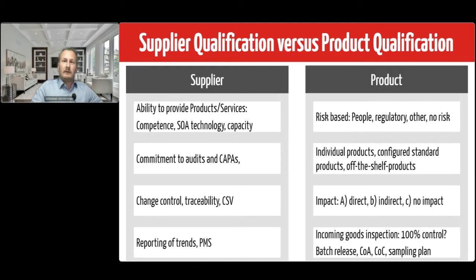And on the product side, they need to have a risk-based approach and estimate what the risk for people is, what the regulatory risks are, other or no risks, and based on that classification, the efforts can be estimated. And it's also different if it is an individual product purchased, if it's a configured standard product, or if it's an off-the-shelf product. And is the impact direct, is it indirect, or does it have no impact? So thereby the efforts can also be estimated. And controlling this can be done by incoming goods inspection, like 100% control, or isn't 100% control necessary? Is something such as batch release within the laboratory necessary? Do you need a certificate of analysis, certificate of compliance, or may a sampling plan be appropriate?